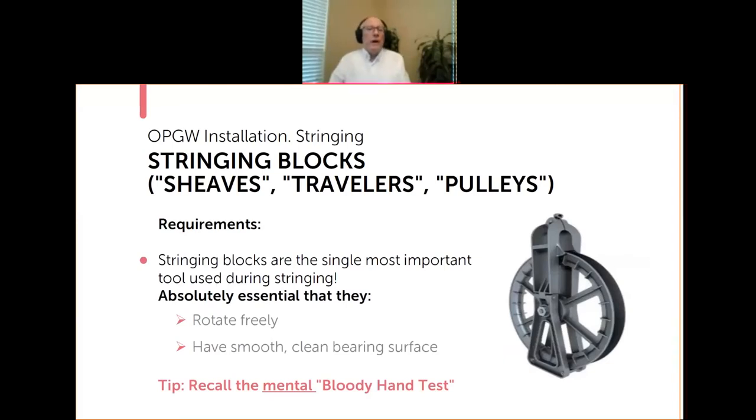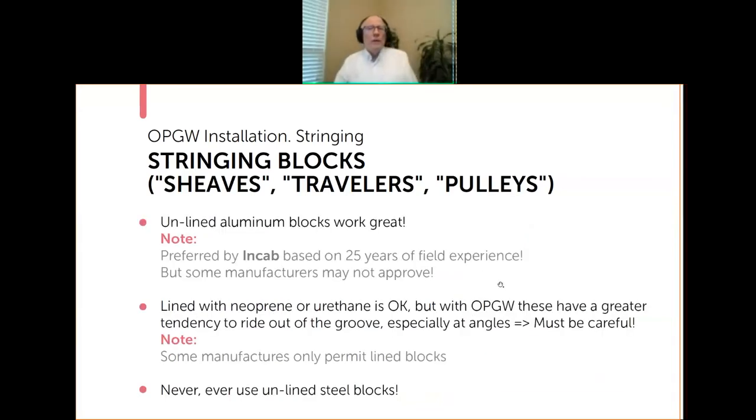Stringing blocks — also called sheaves, travelers, or pulleys — are the single most important tool used during the stringing process. It's absolutely essential that they rotate freely and have a smooth, clean bearing surface. Remember that mental bloody hand test — if you would be afraid to put your hand in this groove and rotate the block because you think it would come out a bloody mess, that's not a good block to use.